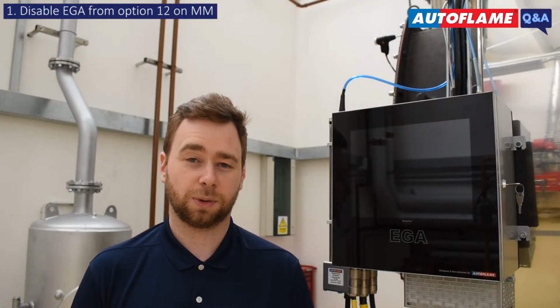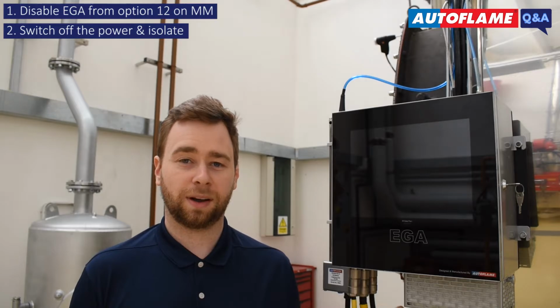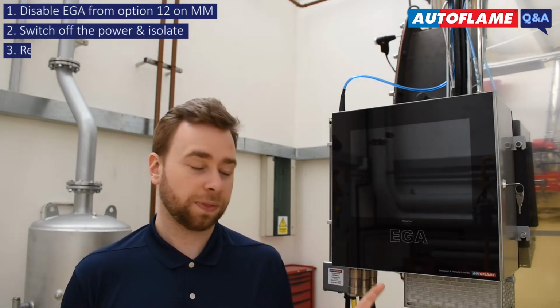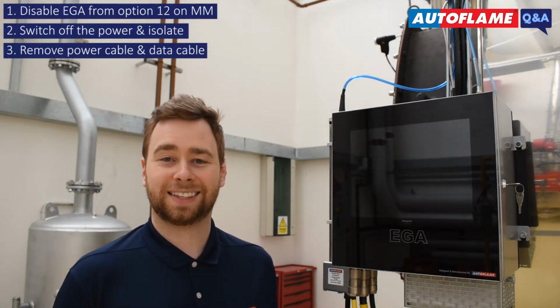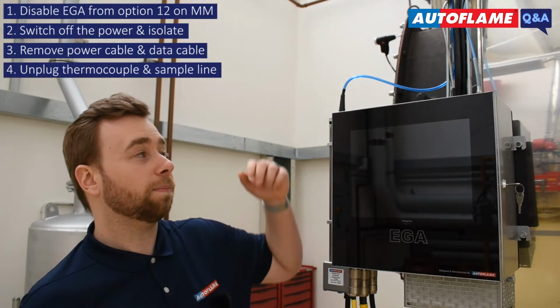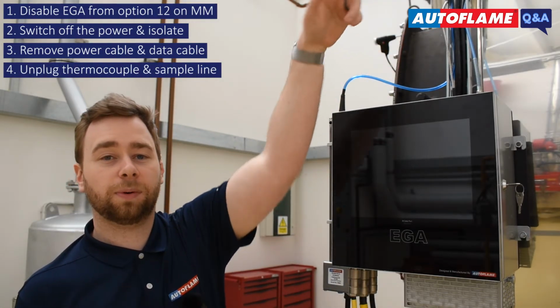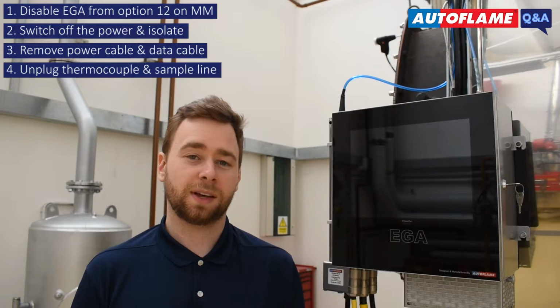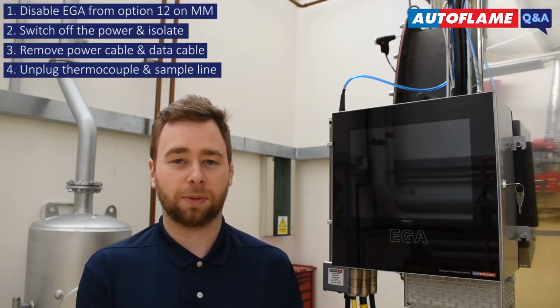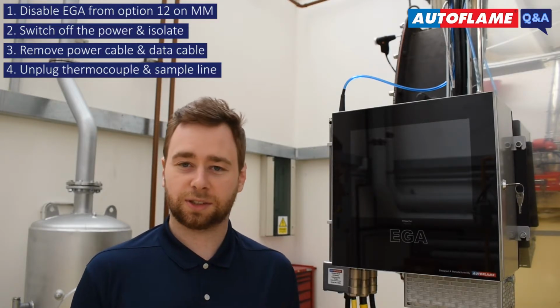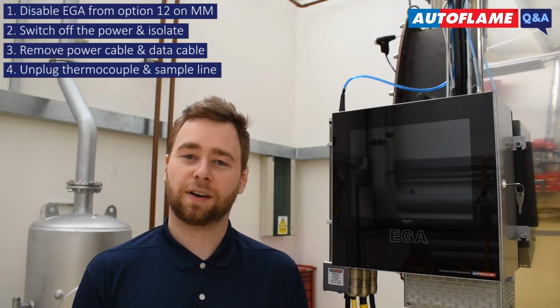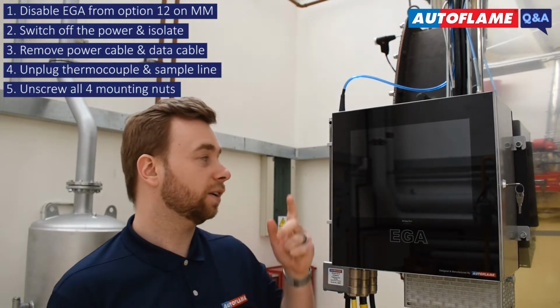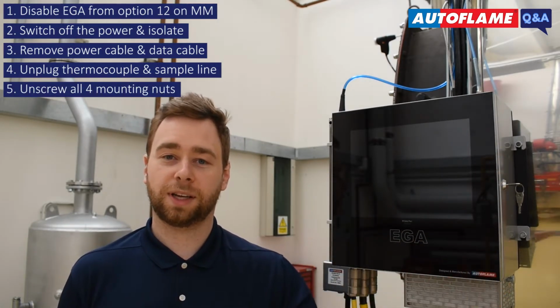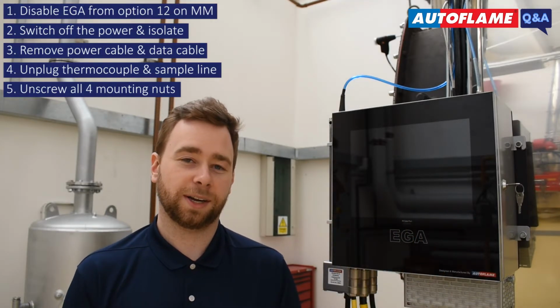To prepare your EGA for service, you need to disable the EGA from option 12 in the MM, switch off the power and isolate the power to the EGA, remove your power cable and data cable from underneath the EGA, and then unplug your thermocouple and sample line connector from the top of your EGA. You can leave these hanging, but you may want to plug up the bottom of your sample line just to stop any dirt from entering. Finally, there are 4 mounting nuts, 2 on either side. Unscrew these and you can lift off your EGA.